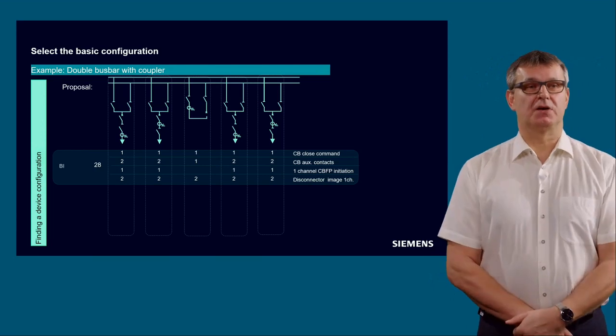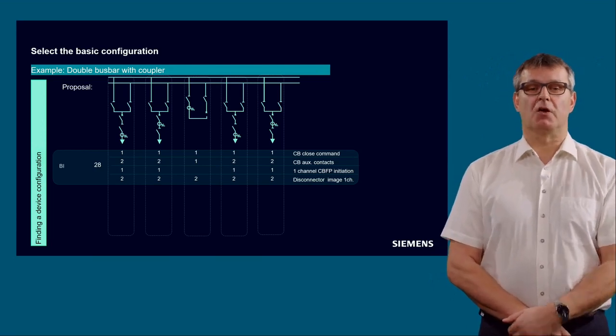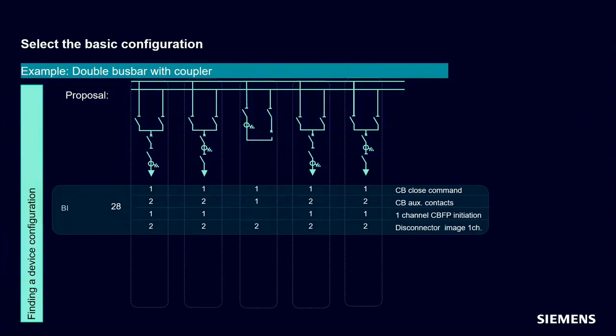The auxiliary contacts of the circuit breaker, you need, okay, I forgot the close command. Here, 1 binary input is enough, both for the feeders and for the coupler. The circuit breaker auxiliary contacts for the position of the circuit breaker, which is necessary not for the disconnector image, but for the end-fault protection. We need 2 binary inputs in the feeder, and in the coupler, 1 binary input may be enough, because here the coupler current is not part of the check zone anyway, so here the security requirements may be a little bit lower.